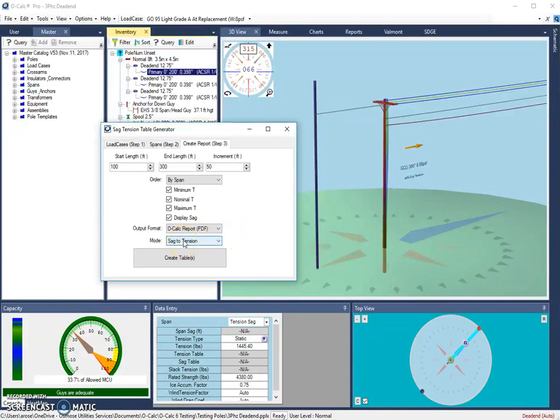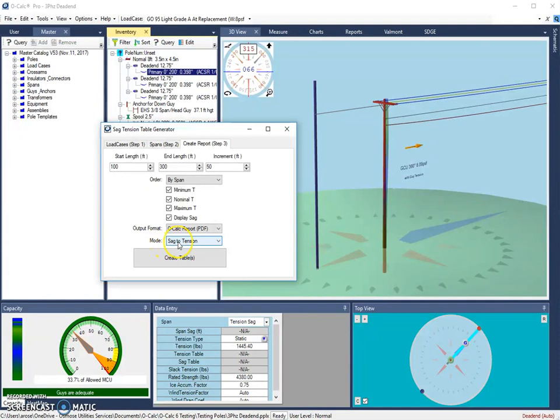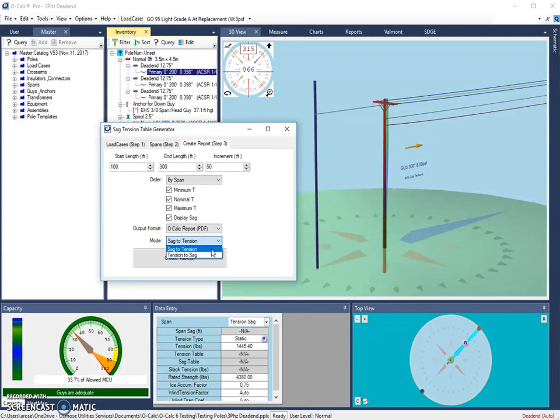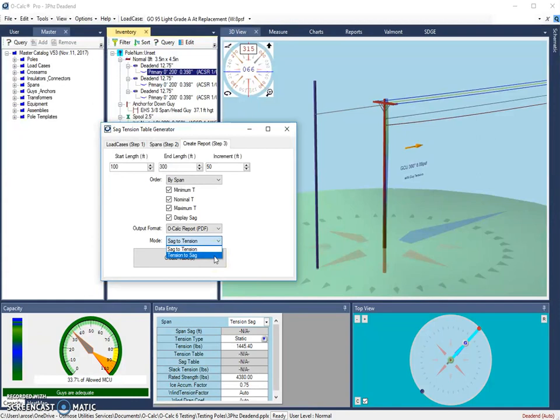Lastly, you can choose the mode that you want to look at. So this relates to different tension modes that can be used. There are separate wiki page articles specifically on this topic on the O-Calc Pro wiki page. But essentially you need to choose between Sag to Tension or Tension to Sag. When Sag to Tension is used, the software is using a sag value and calculating what the tension would be based on that sag value. In Tension to Sag mode, it's looking at an initial stringing tension and calculating what the sag is going to be. So that's the mode I'm going to use if I'm more interested in what the sag values are.